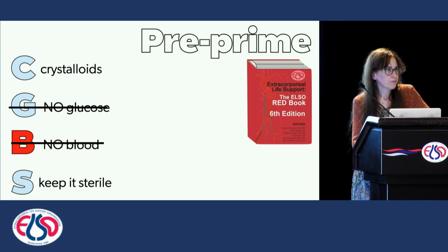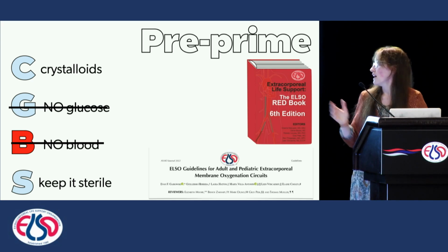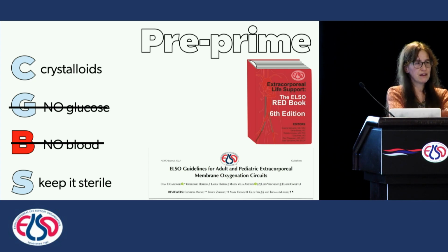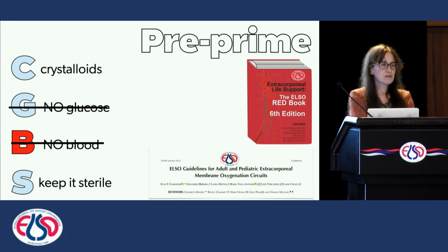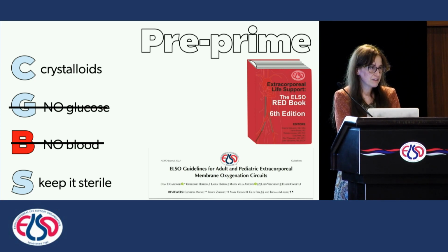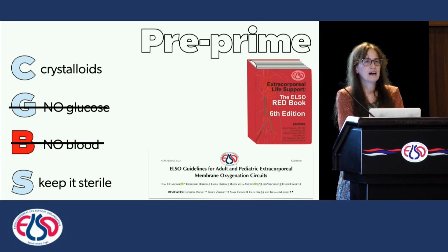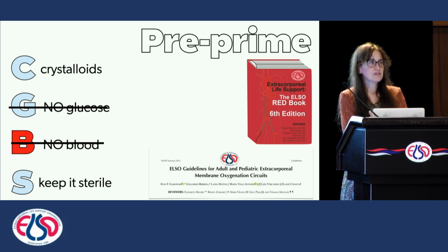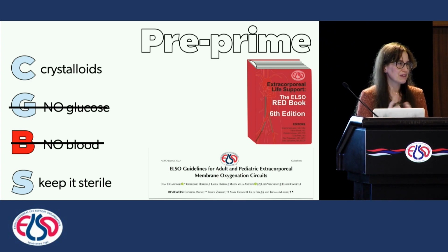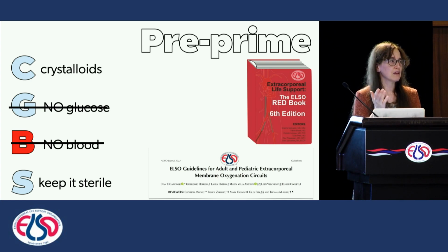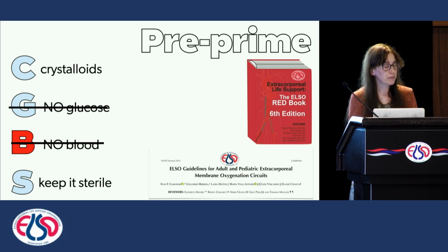How long should we keep this pre-primed circuit? Again, I do not have the definite answer. It is advised in the most recent ELSO guideline for the ECMO circuit that you could keep this circuit for at least 30 days and it is stable. We, again, have some literature saying that it could be safe up to 60 days or maybe more. It's up to you to choose whether to keep a circuit pre-primed or to choose a circuit pre-assembled but not pre-primed.